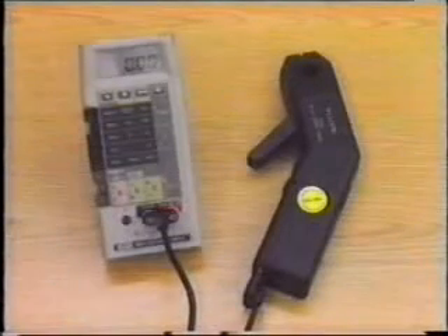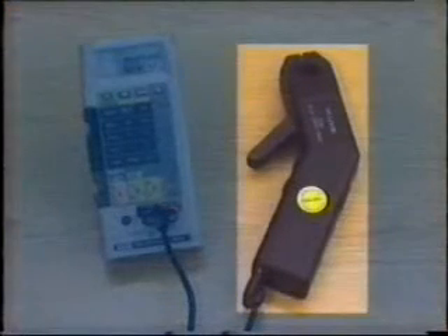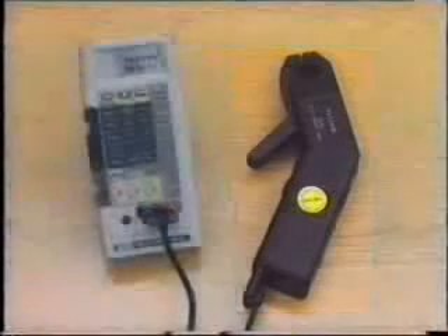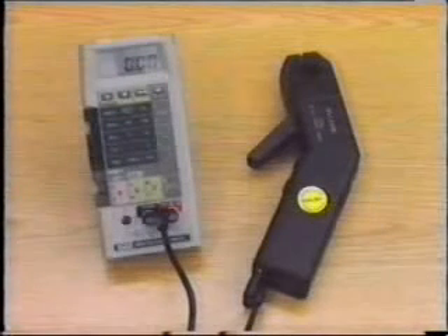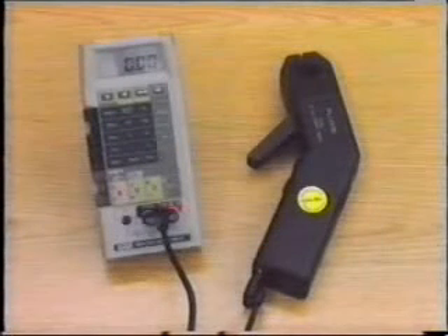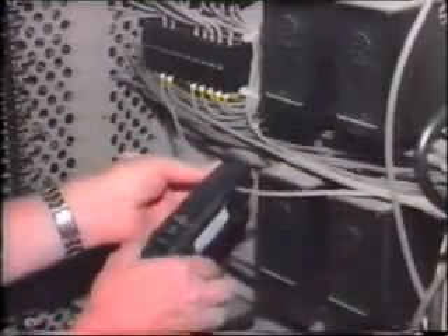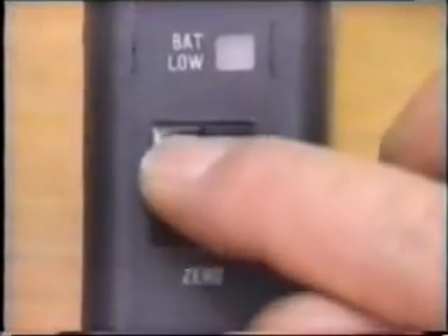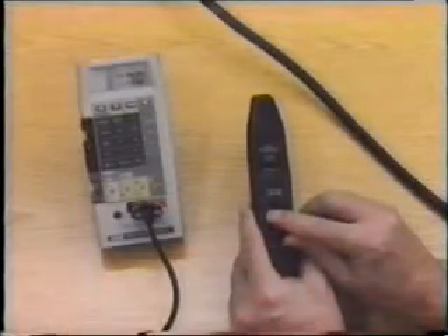Another type of current probe is the Hall effect probe. This probe actually measures the effect of DC and AC magnetic fields around conductors. In this unit, an internal energy supply is required, so you must remember to check and change the batteries periodically. Although the input signal is current, the output of the Hall effect probe is actually a voltage signal, which can be measured by a DMM. You must remember to zero the output voltage before taking the reading.